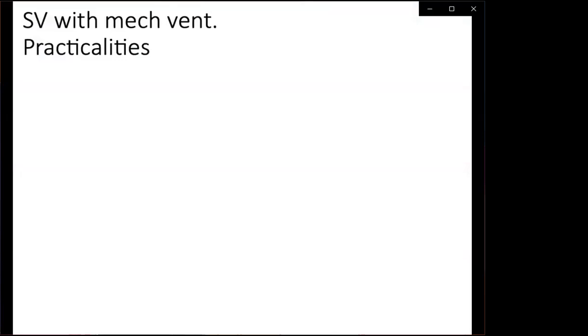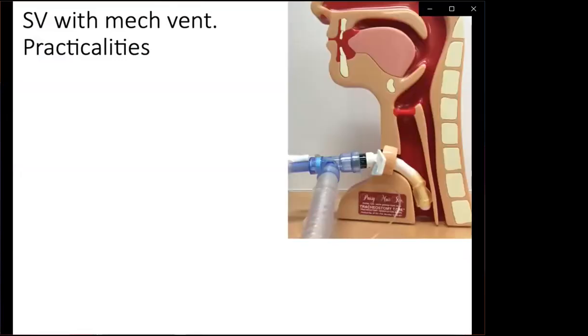And finally, I thought about some practicalities for speaking valve use with mechanical ventilation. In order to put the speaking valve in line with mechanical ventilation, you need to put it as close as possible to the tracheostomy tube. But obviously, most mechanically ventilated patients have inline suction catheters in place. So the best and most practical place to put the speaking valve is on the side port of the inline suction catheter.